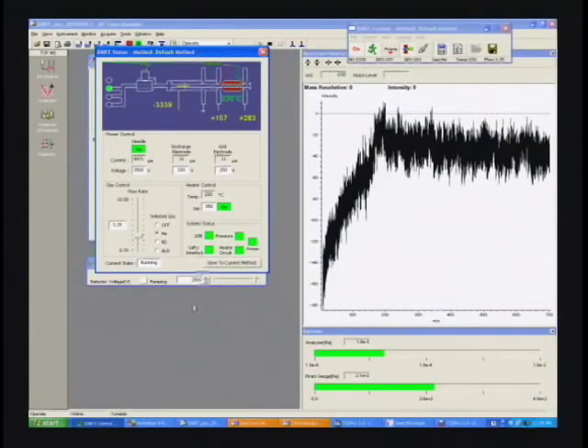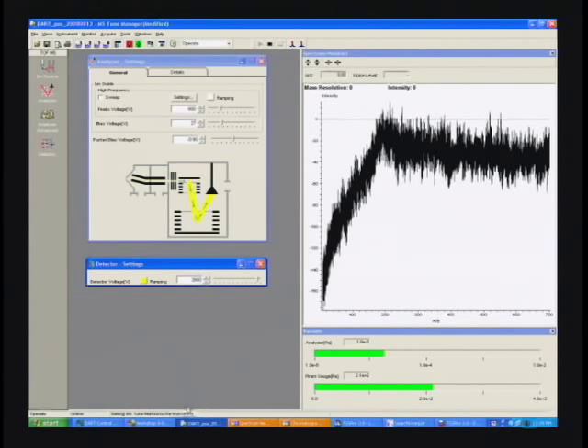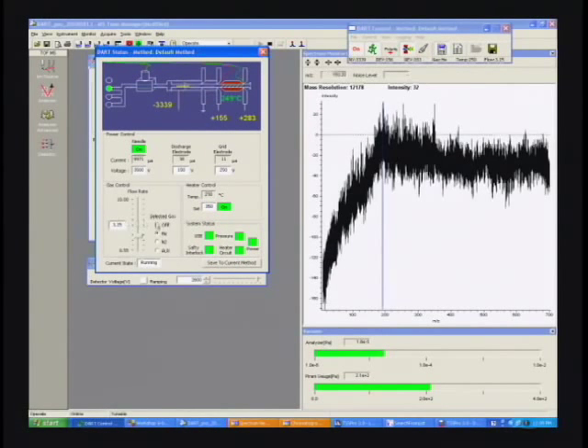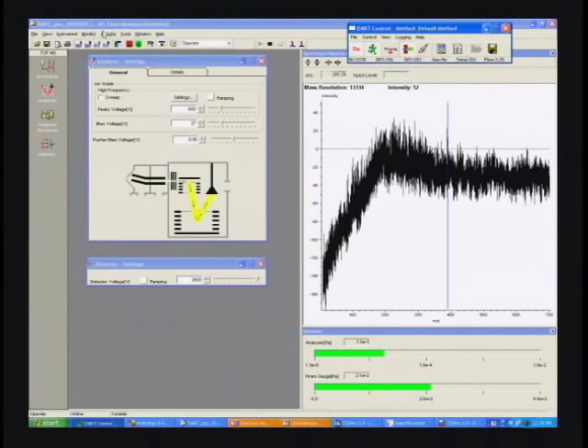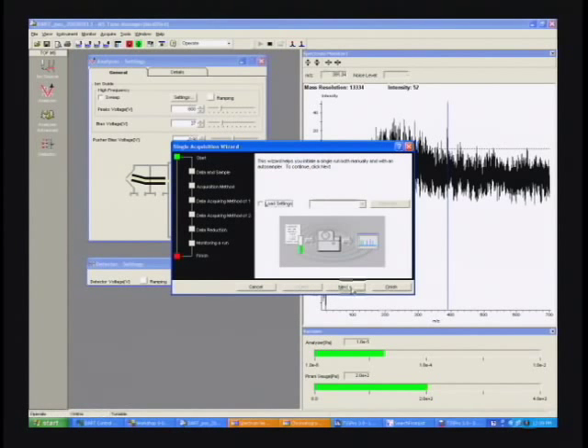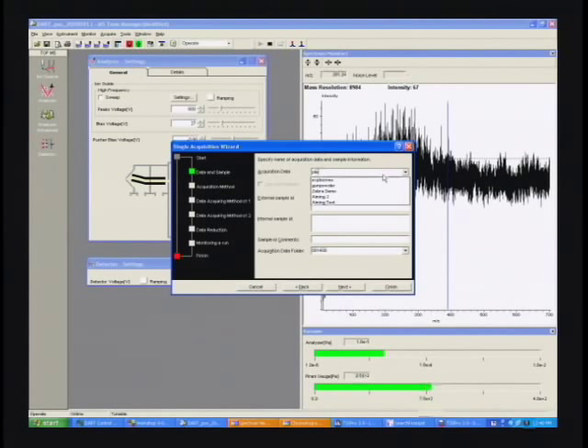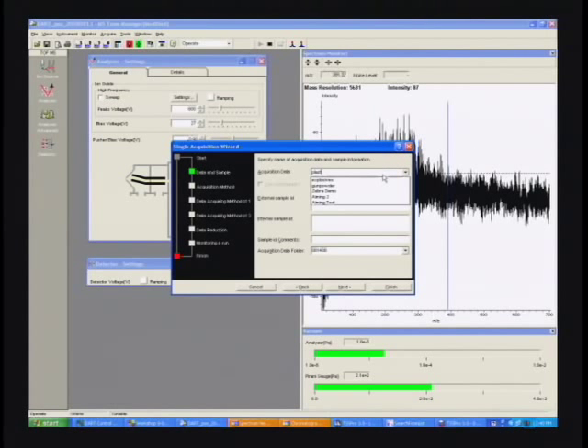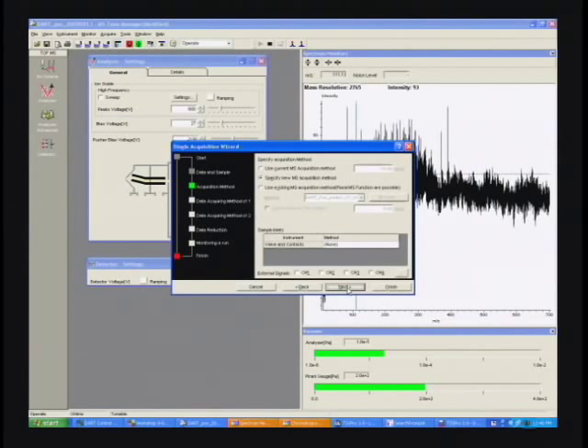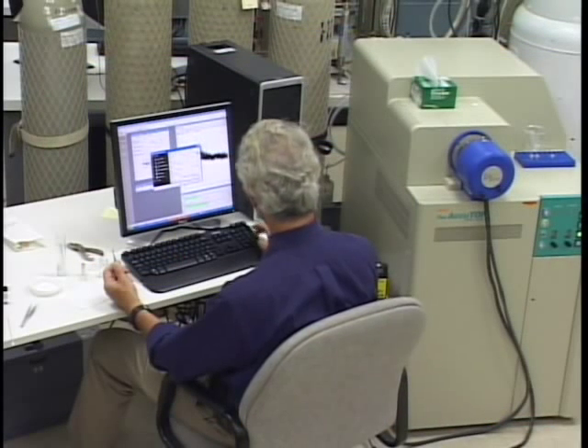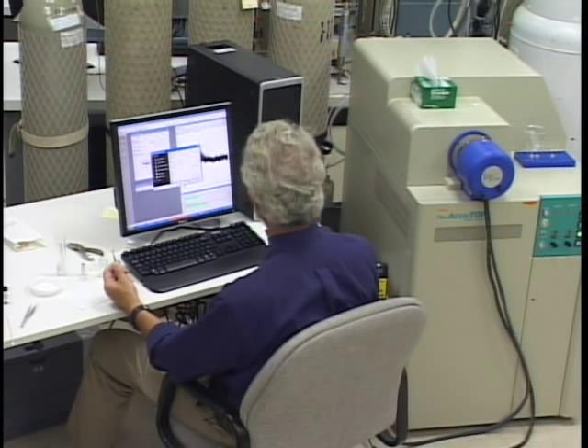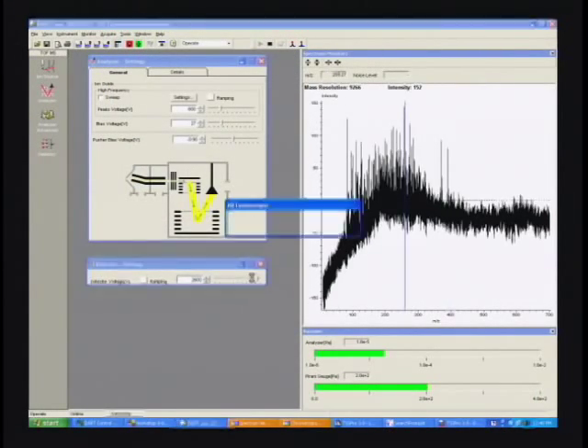We're in operate mode. Let's go ahead and make sure we have some signal. I think everything's on and running. There we go. Now let's set up a data acquisition. Let's just call it plastic. Let's go to a little higher mass, let's say 1,000. Some of the polymers can give you higher mass peaks and those are characteristic. So we might as well go ahead and measure them. Some of the additives are also around the 600 to 700 mass range. So it's good to have a higher mass range for this. We'll see the window open up. As soon as we hit the start button, we'll start collecting.